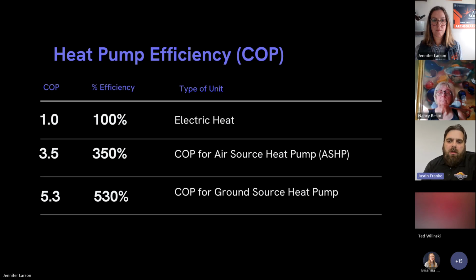And then our geothermal is always going to be our most efficient option. We offer a Water Furnace 7 series, which is their modulating water-to-air unit that runs a COP of 5.3. So we're buying that one part and basically making 5.3 parts off of the refrigerant and the constant temperature of the ground.